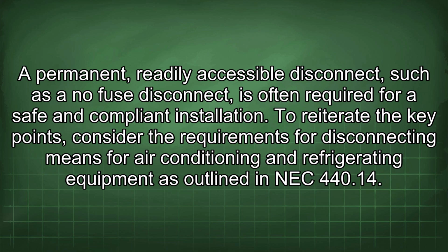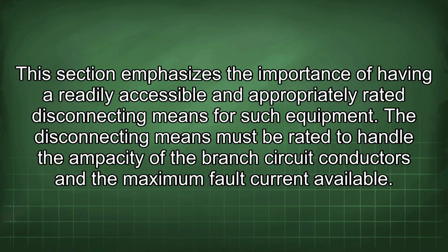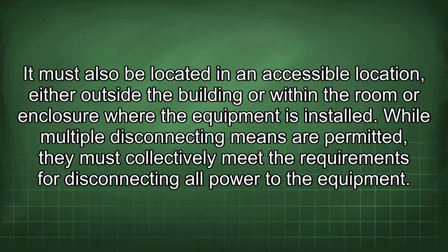To reiterate the key points, consider the requirements for disconnecting means for air conditioning and refrigerating equipment as outlined in NEC 440.14. This section emphasizes the importance of having a readily accessible and appropriately rated disconnecting means for such equipment. The disconnecting means must be rated to handle the ampacity of the branch circuit conductors and the maximum fault current available. It must also be located in an accessible location, either outside the building or within the room or enclosure where the equipment is installed. While multiple disconnecting means are permitted, they must collectively meet the requirements for disconnecting all power to the equipment.